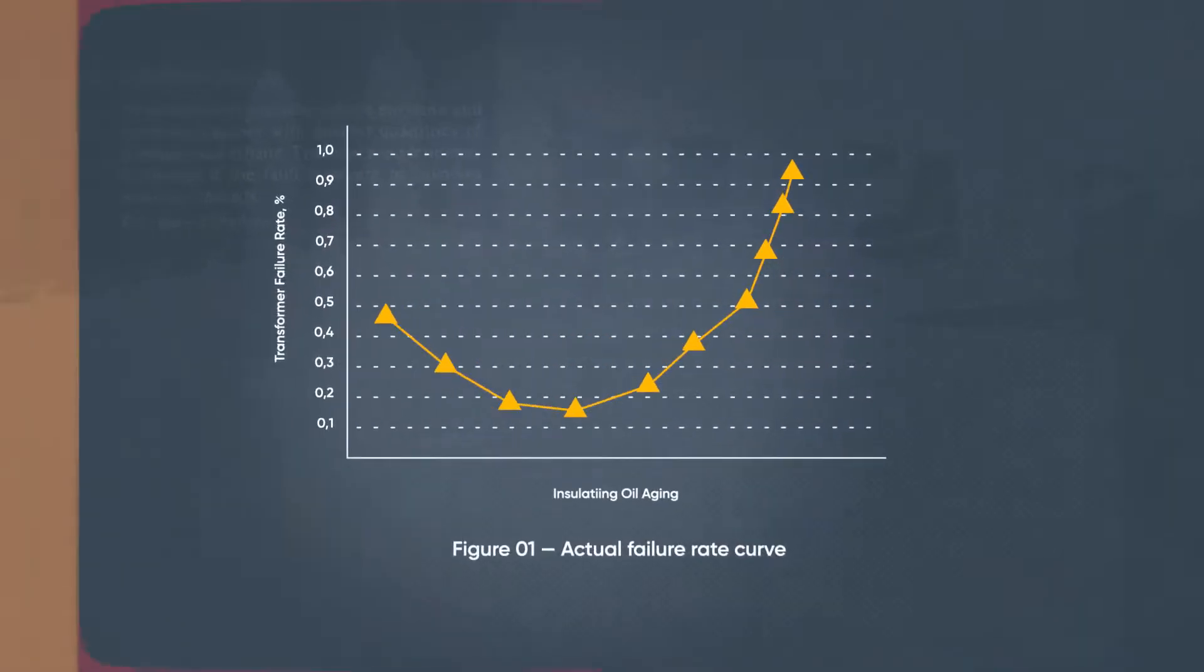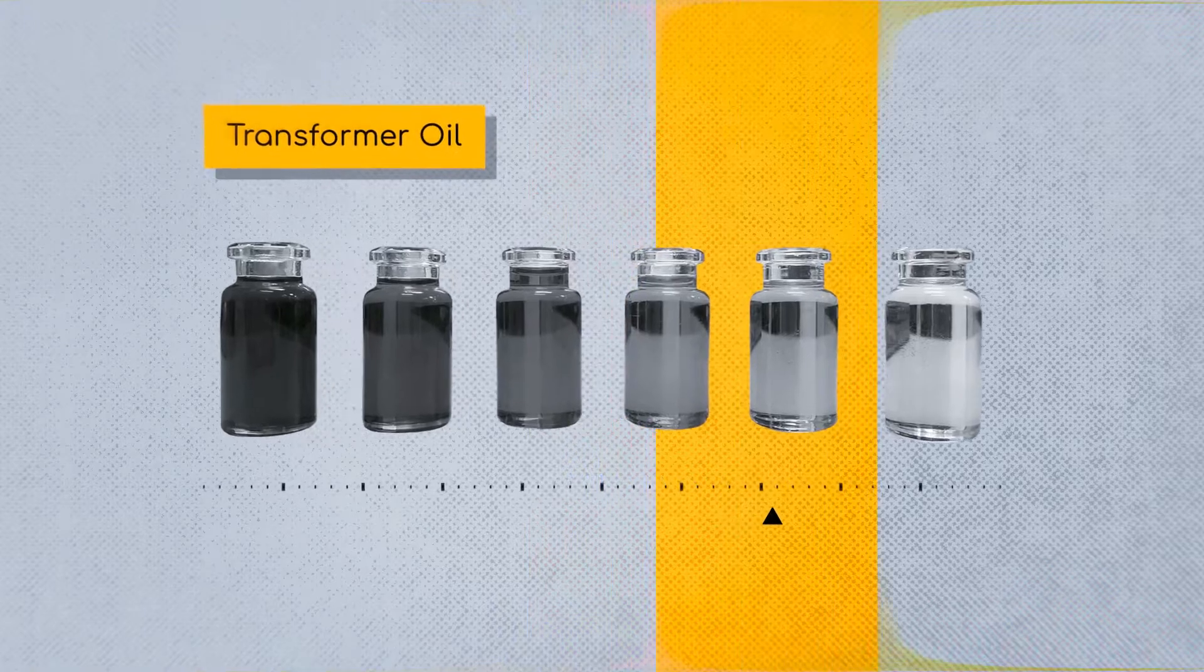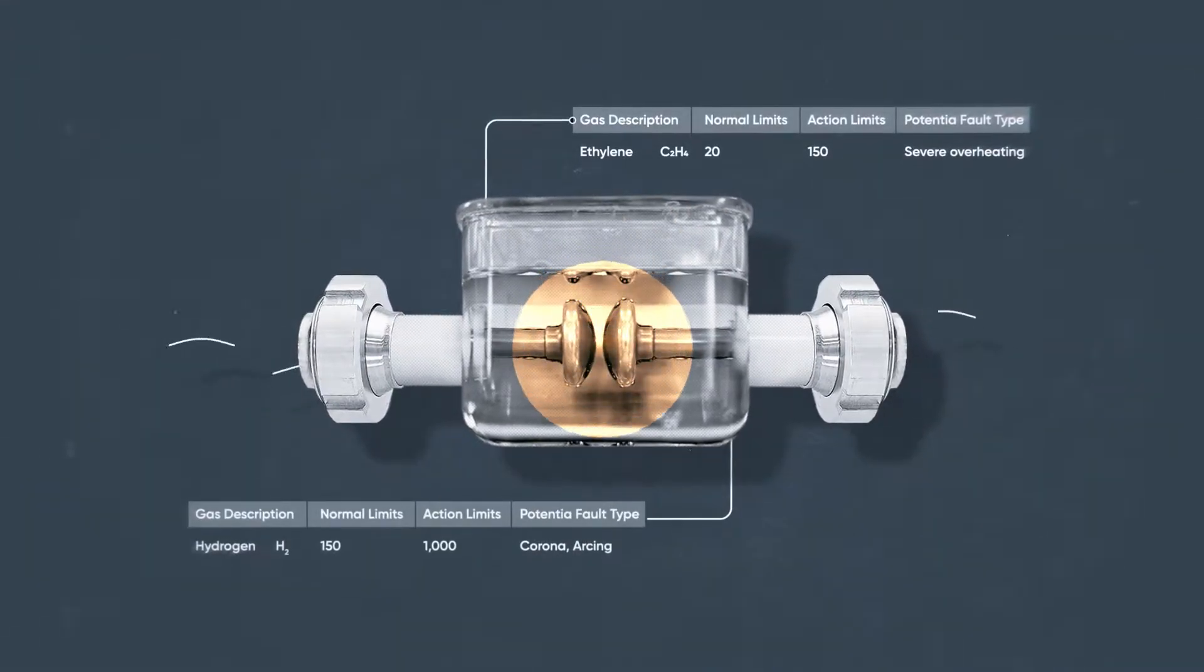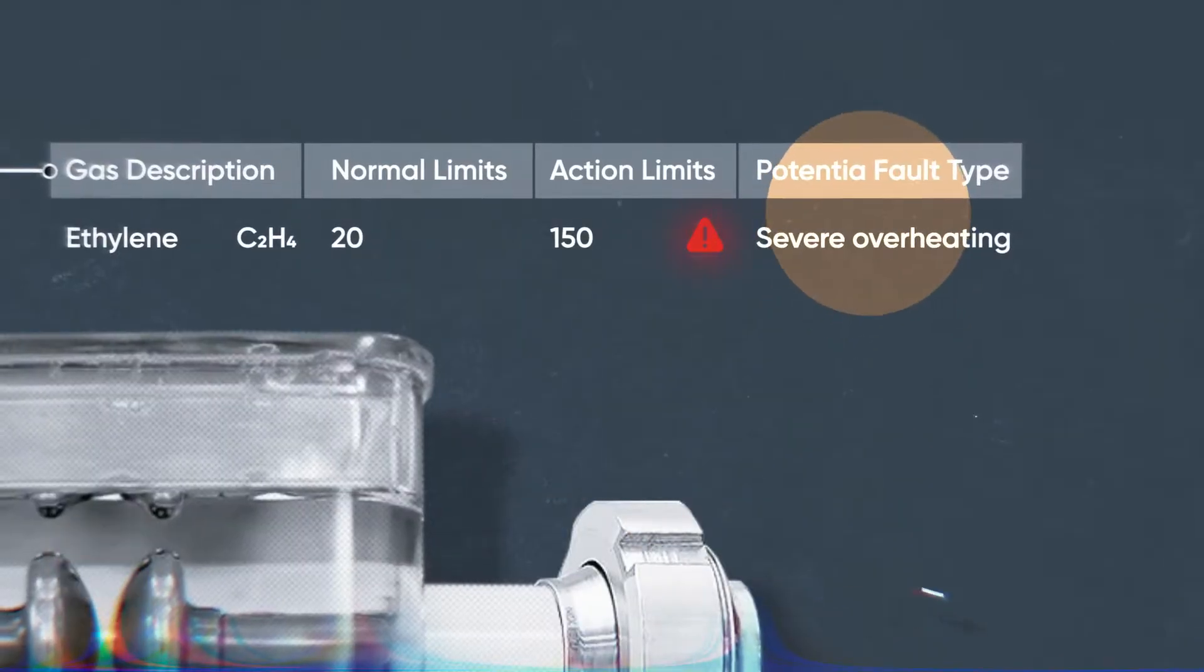The overall performance of transformers highly depends on the condition of the oil, which plays the role of a dielectric, heat transfer agent, and arc quencher. That is why regular monitoring of the oil enables potential problems to be diagnosed.